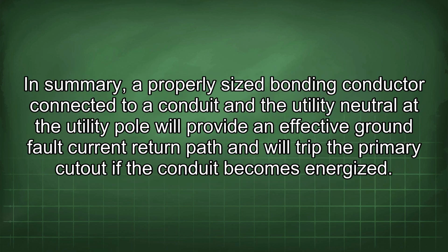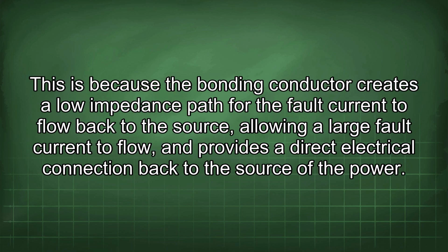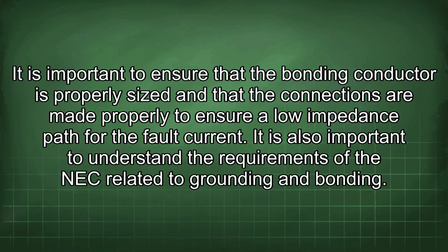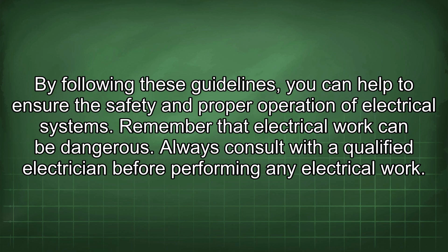In summary, a properly sized bonding conductor connected to a conduit and the utility neutral at the utility pole will provide an effective ground fault current return path and will trip the primary cutout if the conduit becomes energized. This is because the bonding conductor creates a low impedance path for the fault current to flow back to the source, allowing a large fault current to flow, and provides a direct electrical connection back to the source of the power. It is important to ensure that the bonding conductor is properly sized and that the connections are made properly to ensure a low impedance path for the fault current. It is also important to understand the requirements of the NEC related to grounding and bonding. By following these guidelines, you can help to ensure the safety and proper operation of electrical systems.